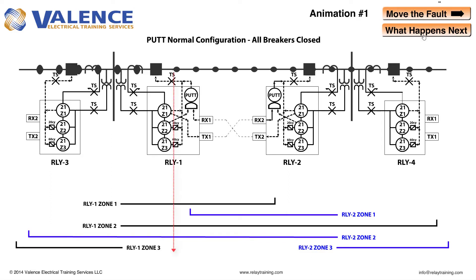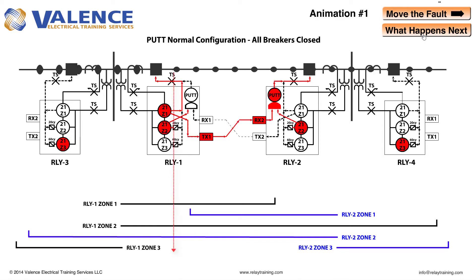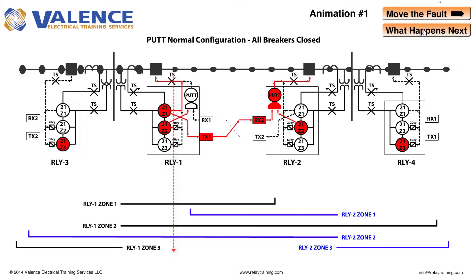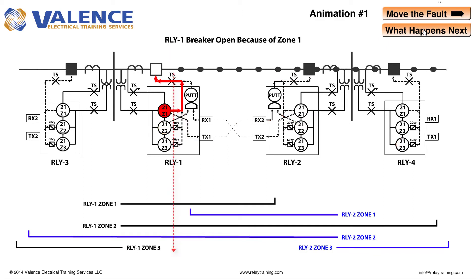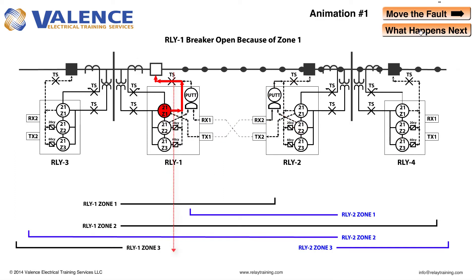Which elements will pick up in Relay 1 if a fault occurs close to Relay 1 as shown here? Which elements will pick up in Relay 2? Zone 1 and Zone 2 will pick up in Relay 1 because the fault is closest to Relay 1, while only Zone 2 will pick up in Relay 2. Relay 1 will trip instantaneously because of the Zone 1 pickup, but it will also send a PUTT signal to the other relay because it has detected an underreaching fault on the line. Zone 1 is called an underreaching condition because it is purposely set somewhere between 75 to 90% of the line so that it will never operate for a fault that's not on the line. So right now the fault is still on the line even though Relay 1 tripped and current is flowing through Relay 2.